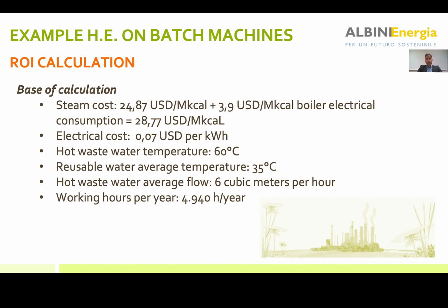This slide shows the return of investment calculation. We started from the steam cost that the company was paying. It was around 25 US dollar per megacalorie. And then we added 3.9 US dollar per megacalorie, which are more related to the pump consumption of the thermal oil.